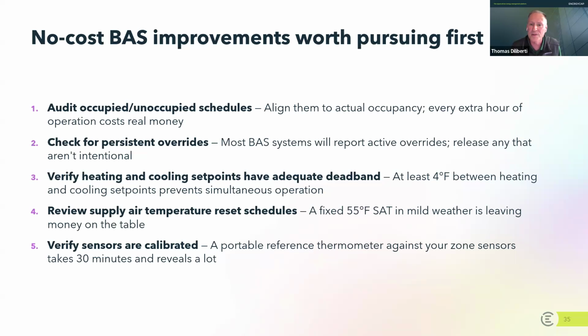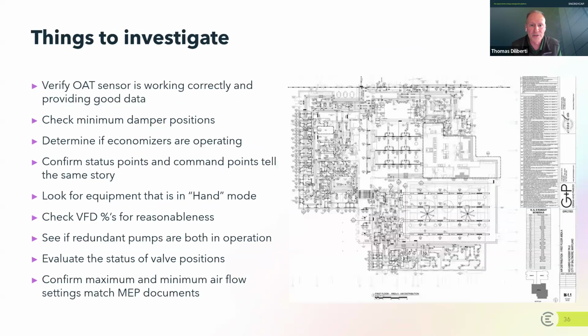The reset schedule is just so important to make sure that you're not overheating or overcooling or creating too much heat or cold unnecessarily. And just make sure you're verifying your sensors, that they're calibrated in some type of regimen. Again, your system will not run properly if your sensors get out of calibration. Finally, I think this last slide that I've got, I didn't mention this until now, but you want to make sure your outdoor air temperature sensor is working correctly and providing good data. Your outdoor air temperature sensor drives the decision for a lot of devices in your building. So boilers, chillers, air handling units may run or not run if it's sensing the wrong outside air temperature. So make sure it's giving you an accurate reading.